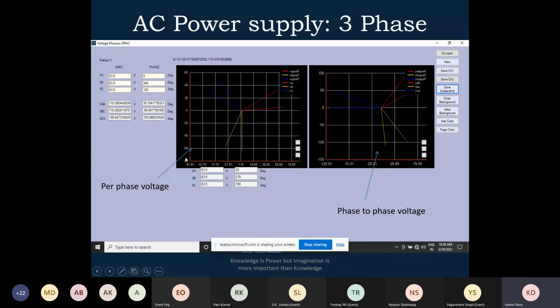So if you look at it here, this is the per phase voltage. On the left side, if you see the screen, you see the phasors, that is the per phase voltage. On the right side, this is the phase to phase voltage. So when we extract the fault data, we need to understand what the quantity is. Many times I have seen in a fault the VA, VB, VC, like VA has not fallen much, but VAB has fallen down. That is why the relay operated. So that is how we have to understand the exact parameters.